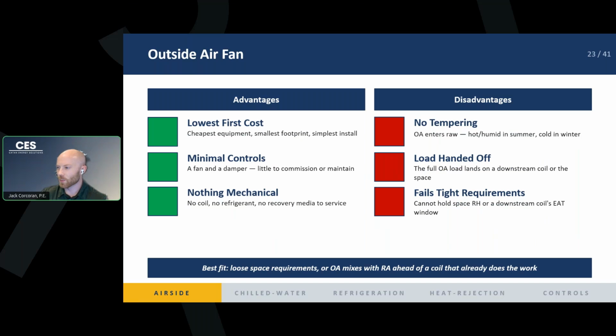You're kind of subject to whatever the outside air temp and humidity is because you're bringing that in directly to the space. So in the bottom right, our best fit is a loose space temperature and humidity requirement, like a warehouse or a garage. And it's best if you mix the outside air with the return air ahead of another coil that is sized for that load, just so you don't dump the raw outside air into your space.